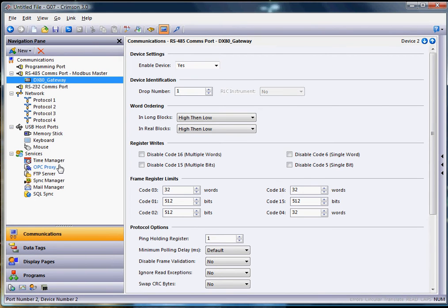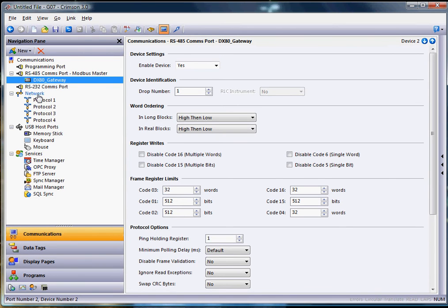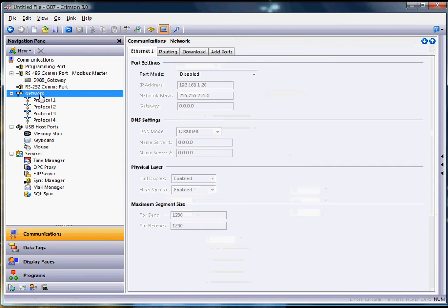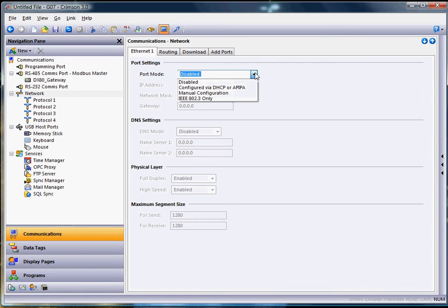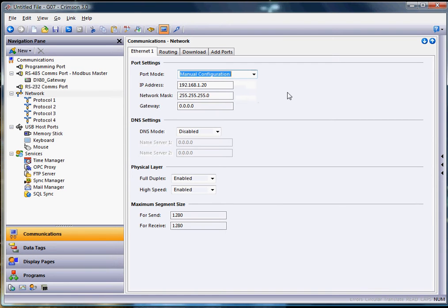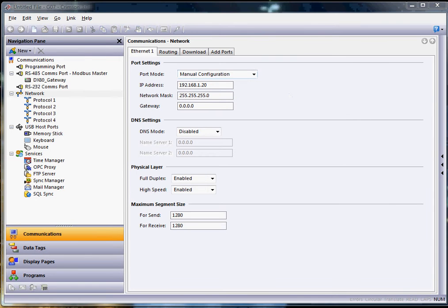What I want to do in this example is take them and migrate their linking from the 485 based communications over to a Modbus TCP. So over here on the left I'll click on the communication section and I'm going to click on the word network because I want to turn on the ethernet port on my Red Lion device. When I click on network right here under Ethernet 1 tab, where it says port mode disabled, hit the pull down and for this example I'll choose manual configuration. Take notice that the default address is 192.168.1.20.